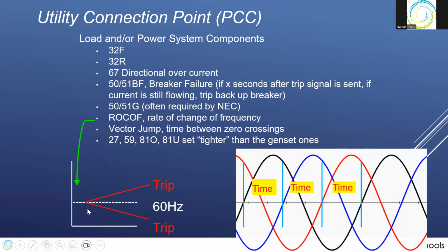ROCOF, rate of change of frequency. So if you're running at some point and you have the possibility to island, that is your generator is feeding local loads outside your system within the utility scheme, then you want ROCOF. Rate of change of frequency, you're going to go up over time or down. The chances of it being balanced perfectly are very slim. And so if you start to do this, you want to trip offline. The UK had trouble with that, so they had to change that setting, but ROCOF has been used some.